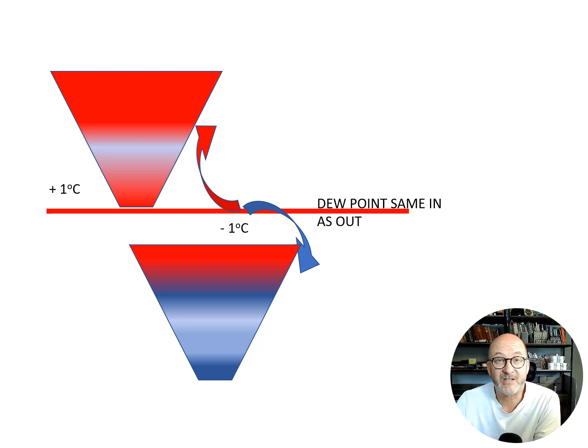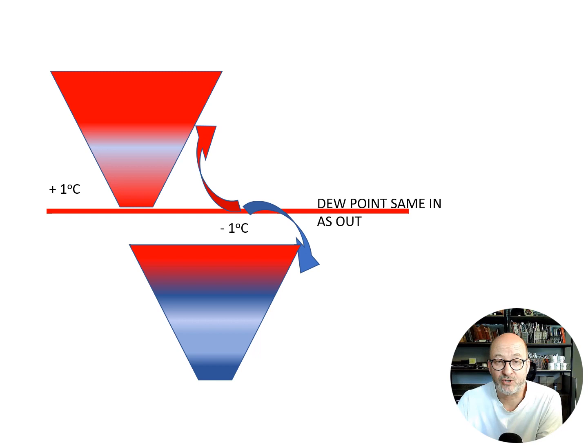One degree above the dew point and the evaporation rate is higher; one degree below and the condensation rate is higher. This is very important when you consider issues such as condensation, ventilation, and movement of moisture through spray foams in roofs. If vapor meets the dew point as it travels through a material, it will turn to water — and that is precisely what we don't want. You can see in this diagram that as the temperature moves away from the dew point, the evaporation or condensation will increase.